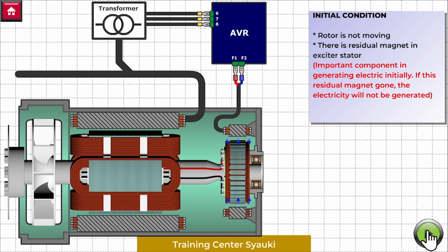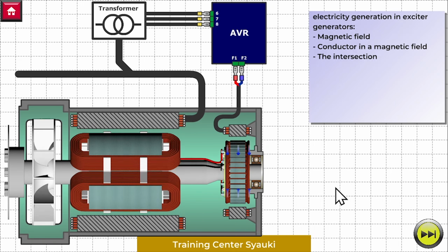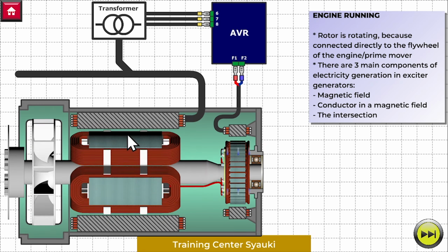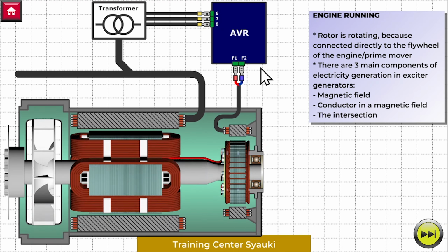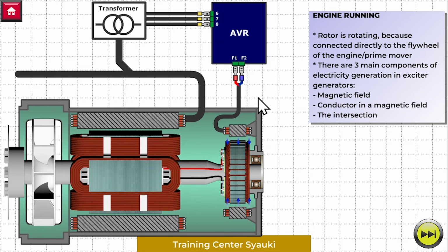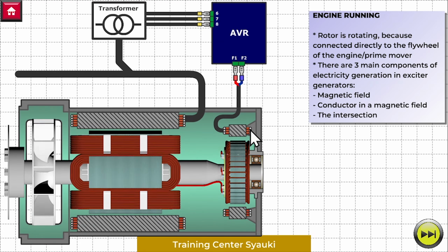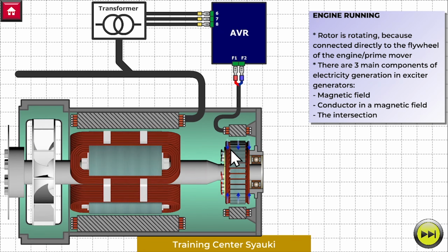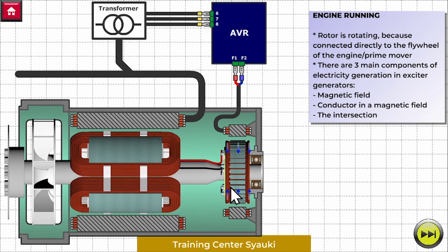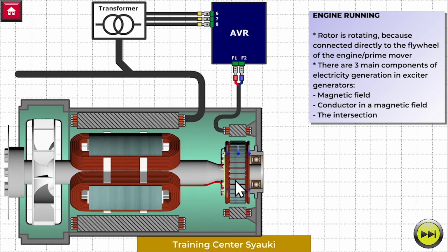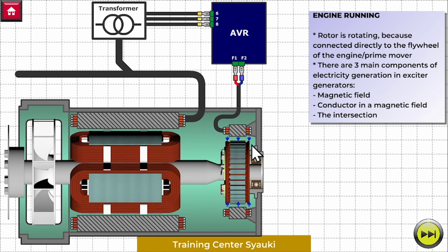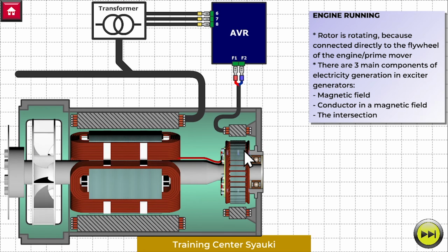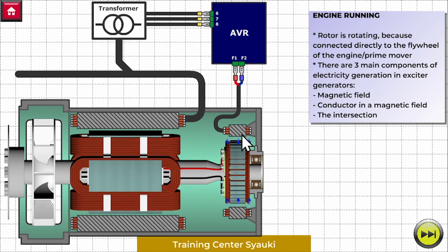Next, after we start the engine, when it rotates, the rotor also rotates. There are three main components of electricity generation in the exciter generator. First is the magnetic field, represented by the residual magnet. Second is the conductor in the magnetic field, which is the exciter rotor. Then the intersection: as we rotate the rotor, the winding in the rotor cuts the magnetic field produced in the exciter stator.